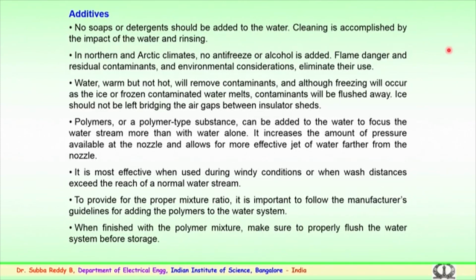The water which is warm but not very hot will generally remove contaminants such as oil. Although freezing will occur as the ice or frozen contaminated water melts, the contamination will generally be flushed away. In such cases, ice should not be left bridging the air gaps between insulator sheds. While removing ice with hot or warm water, care has to be taken that the ice frozen on the insulators is completely melted and removed, and that no bridging remains between the petticoats or sheds, as bridging will bring down the creepage distance of the insulator. So, proper cleaning in case of fog deposits or freezing conditions has to be done.